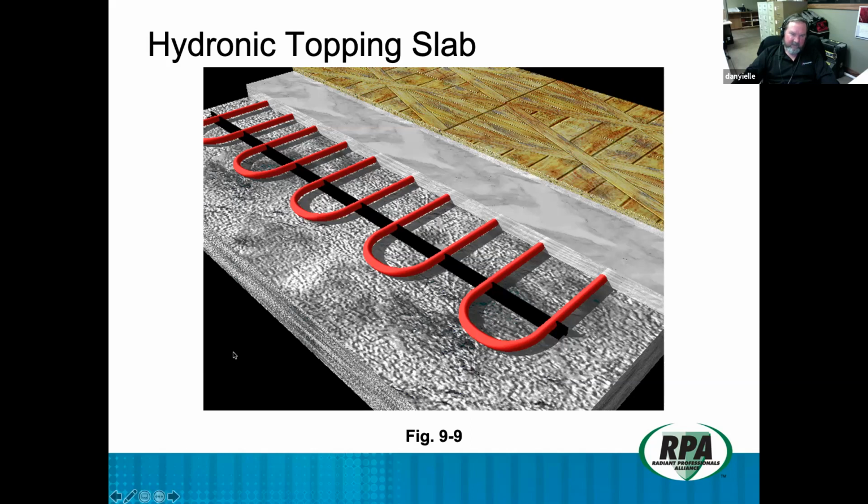Otherwise, you'll get downward or back loss that'll cause a crawl space or a basement to overheat, and it will cause the space that you're trying to condition to underheat. And the typical response is, well, let's turn it up. So they turn the operating temperature up. It makes a little bit of a difference on the top, but it also compounds the back losses into the space below and makes it even warmer yet. That's where we see the Honeywell round thermostat that's been ripped off the wall and the bimetal spring has been completely stretched out. Hey, thought they'd get that puppy to quit heating.